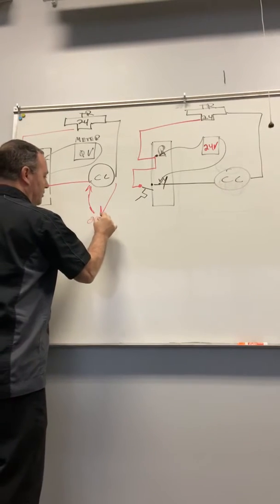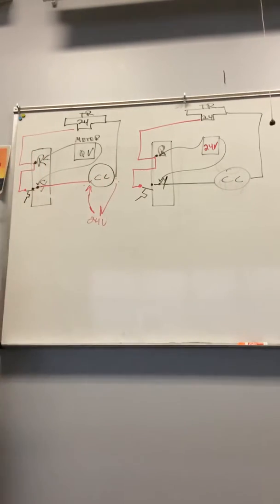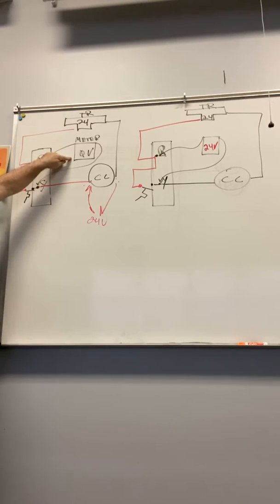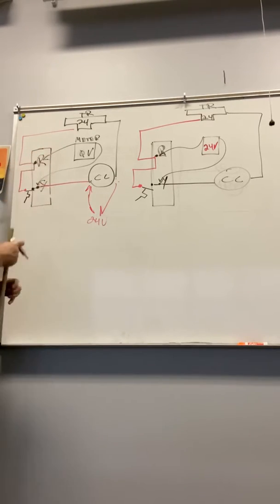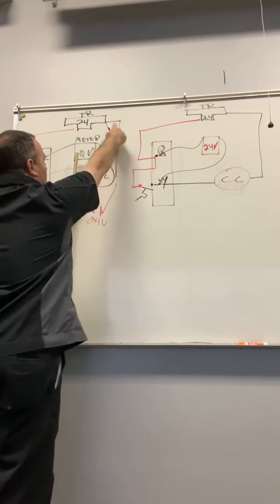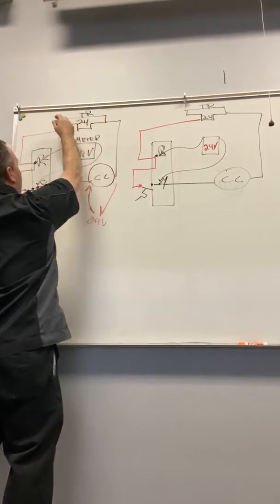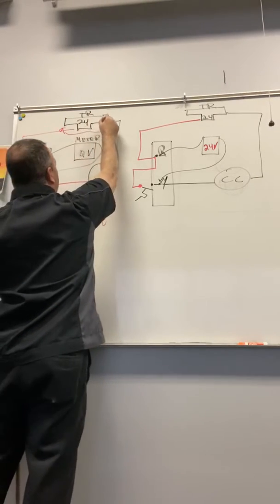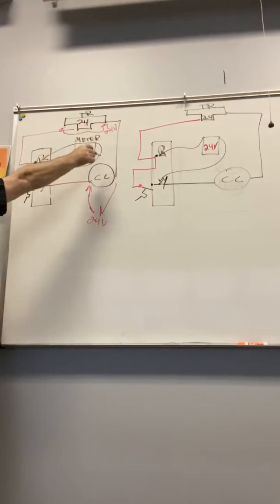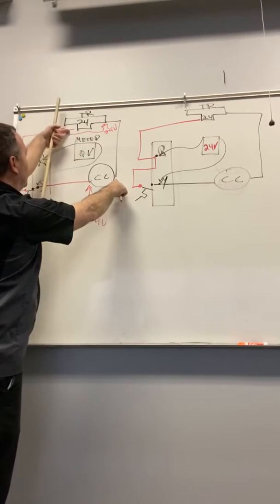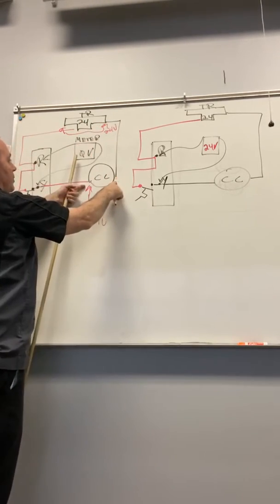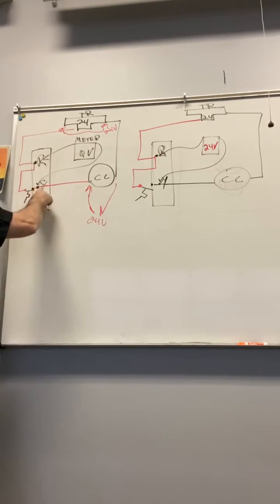That's right, I read 24 volts because I'm on both sides of the circuit. But if I put it between R and Y on a call for cool, I should read 0 volts also, right here, because I'm on this side of the circuit. This is on this side and this is on this side, so if I put my meter here and there, I'd read 24 volts. Here I'm reading 24 volts, because I take that wire and put it here, and this wire right here, I'm reading 24 volts.